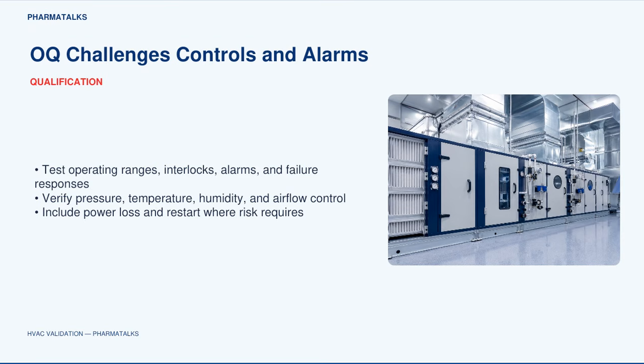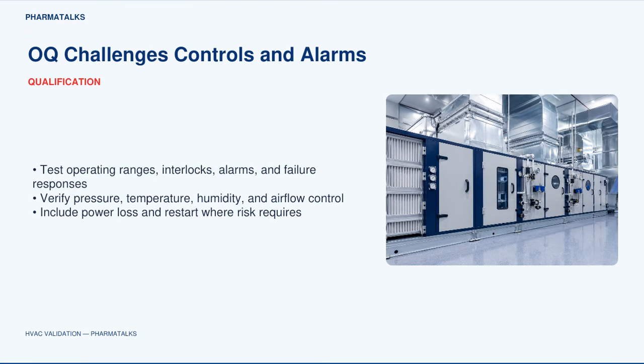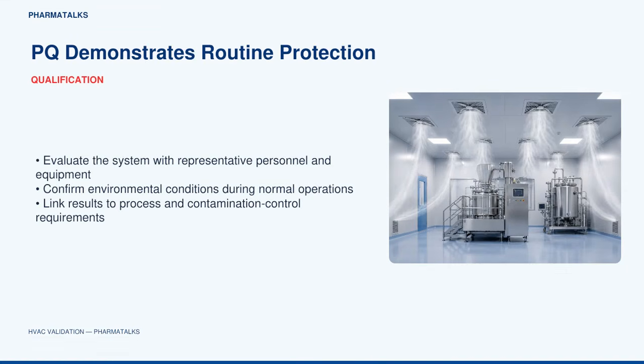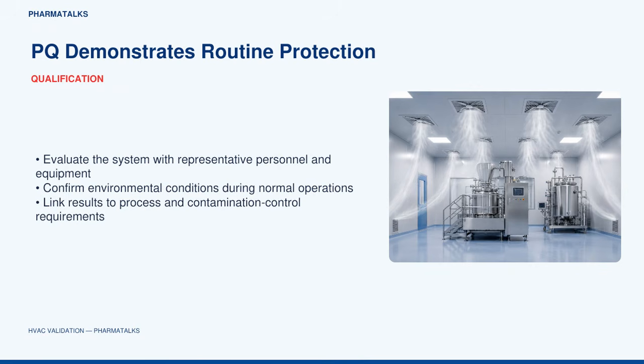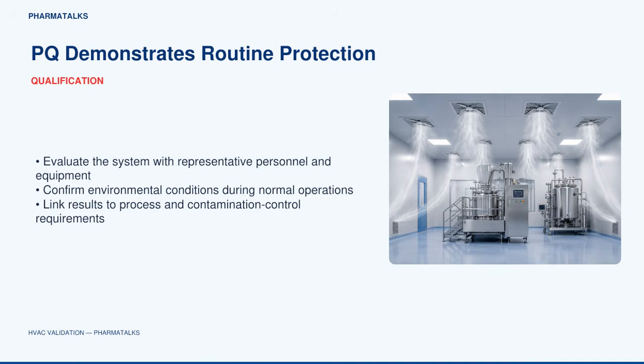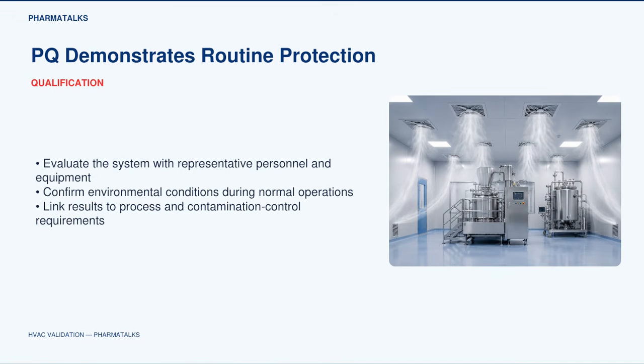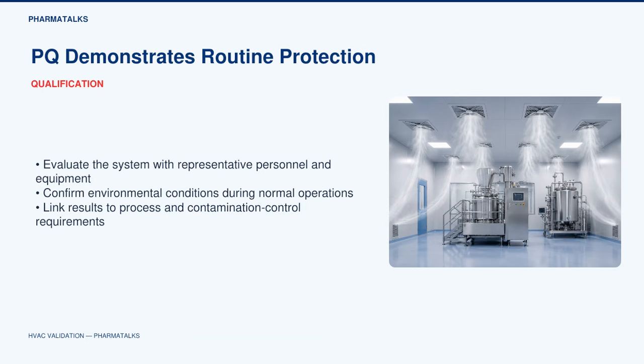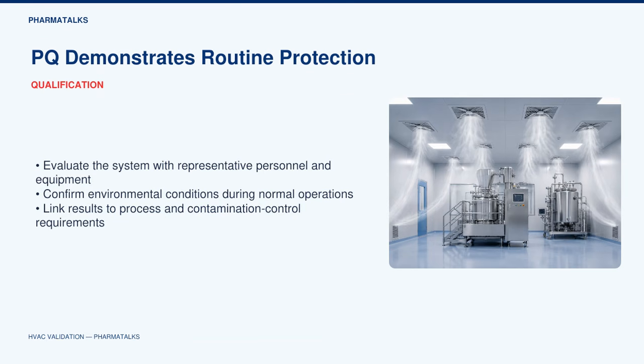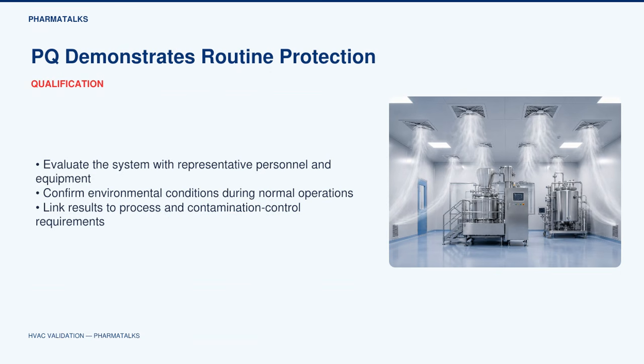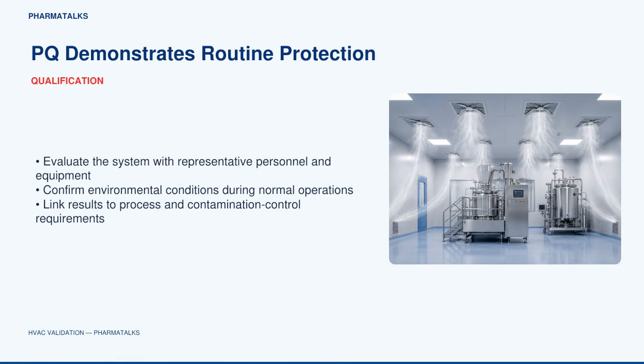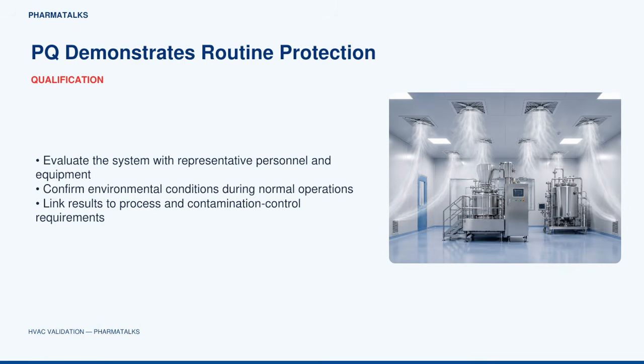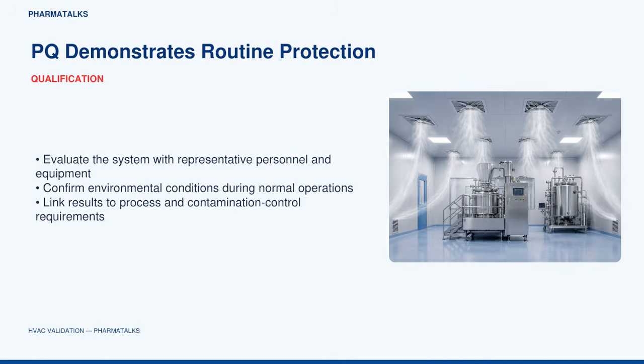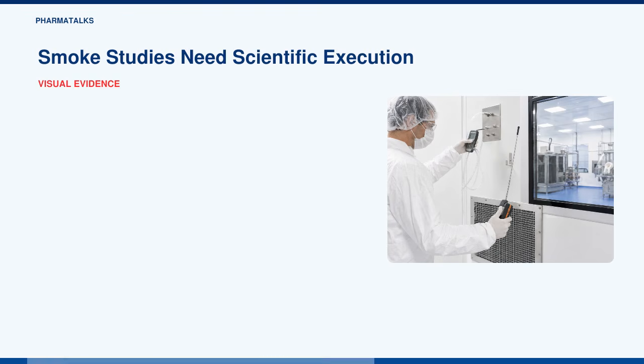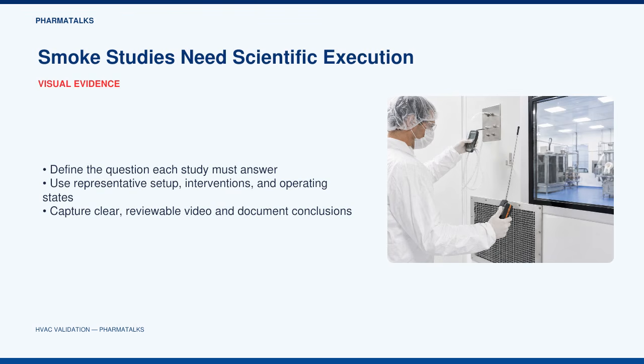Give them a specific, time-bound scenario. Tell the auditor, ask engineering to document the pressure flow during a shift change at the exact moment when both airlock doors are actively transitioning. Oh, that's good. Yeah, that is a highly specific thread. It forces the technical team to prove they didn't just test the airlock doors in a static, perfect environment where nobody is actually moving through the facility. Because the real risk of contamination doesn't happen when the room is empty, it happens when 30 operators are rushing through the airlock to go to lunch, completely disrupting the positive pressure. Exactly. The physics of the room change entirely during a shift transition.